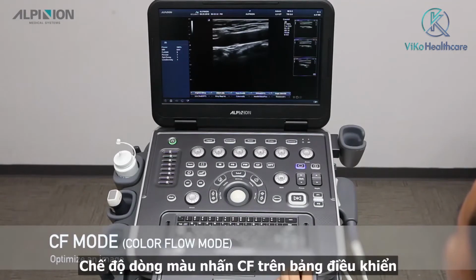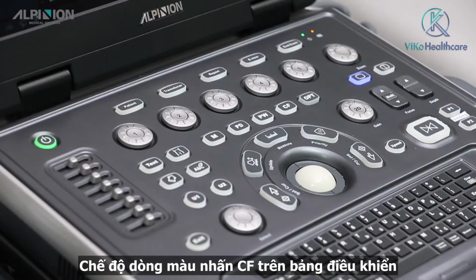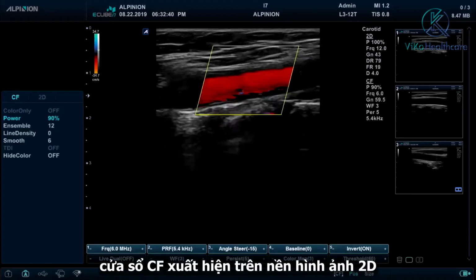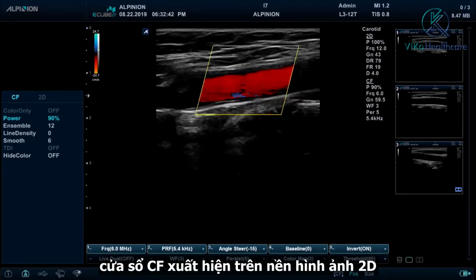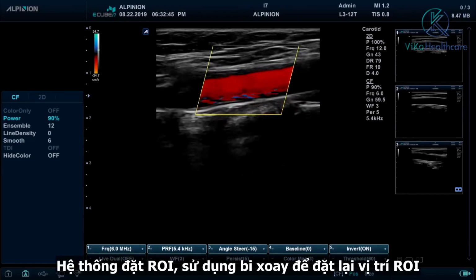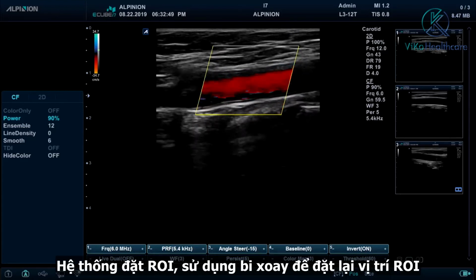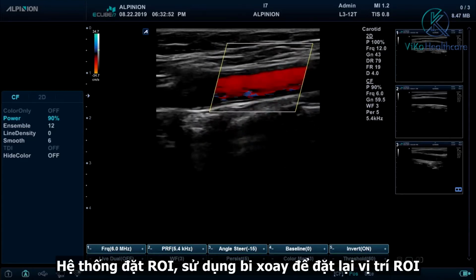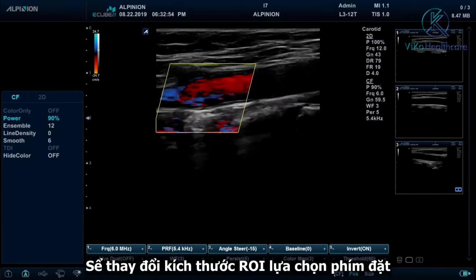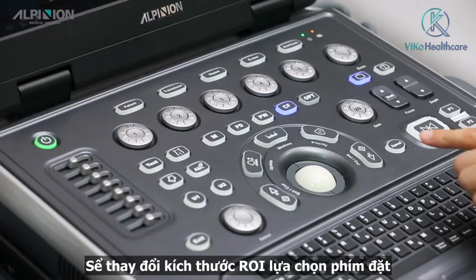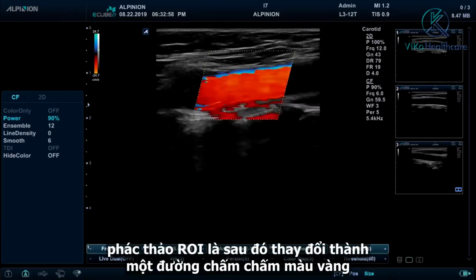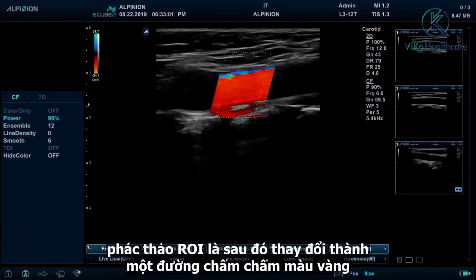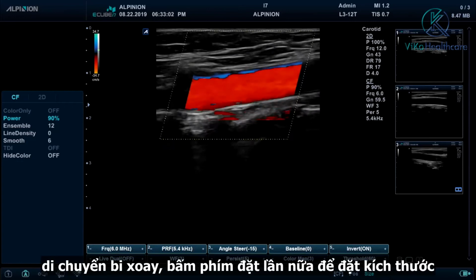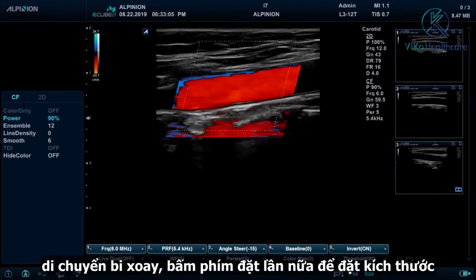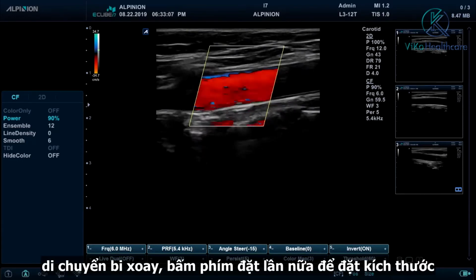Color flow mode. Press the CF key on the control panel. The CF window appears over the 2D mode image. The system places the ROI. Use the trackball to reposition the ROI. To resize the ROI, press the Set key. The ROI outline is changed to a dotted yellow line, then move the trackball. Press the Set key again to set the size.